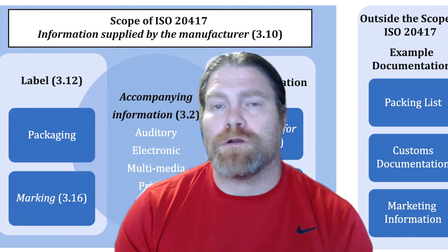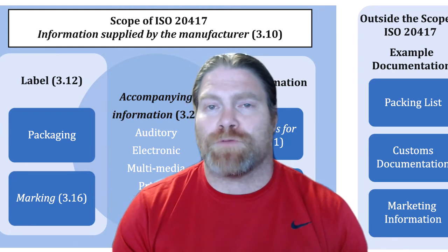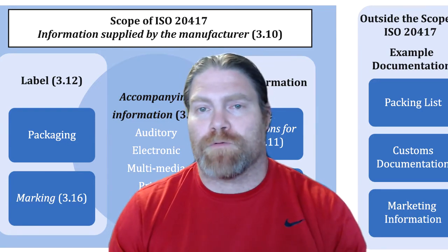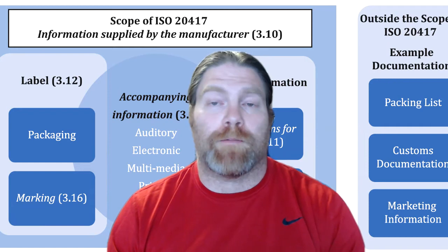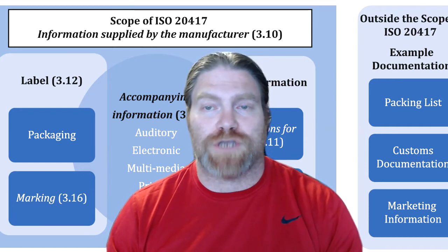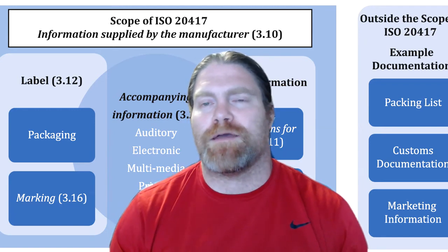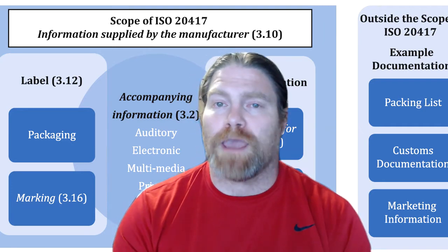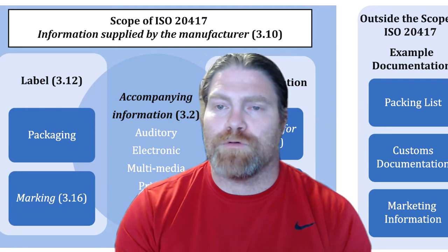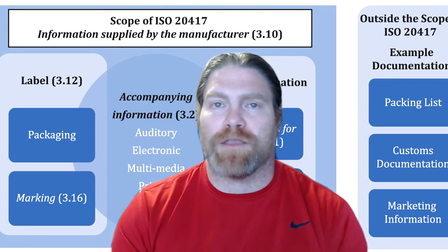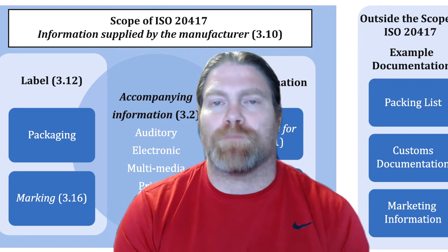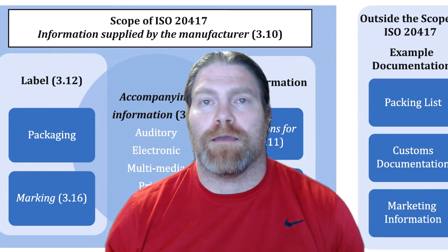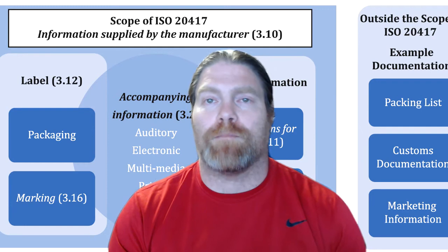And if you want to make it even shorter, you could split it up. 23.1 is the general requirements — you can probably put those directly in the procedure. 23.2 could be a one-page labeling requirements checklist. 23.3 could be a primary sterile barrier label requirements checklist, one page. And then the last one, you could have about a four-page checklist for what needs to be in your instructions for use. Every time you create one of those types of documents, you would review that checklist, document where it can be found in your label or instructions for use, and attach that to the approval of the label or instructions for use.